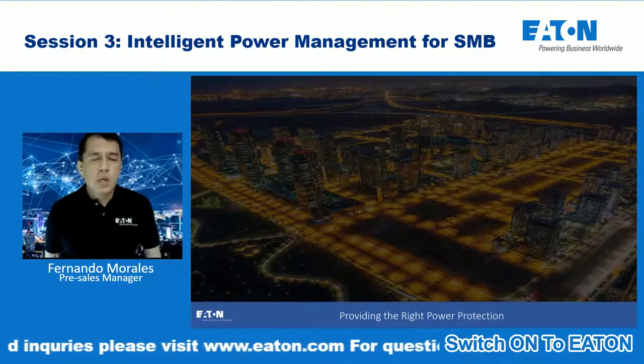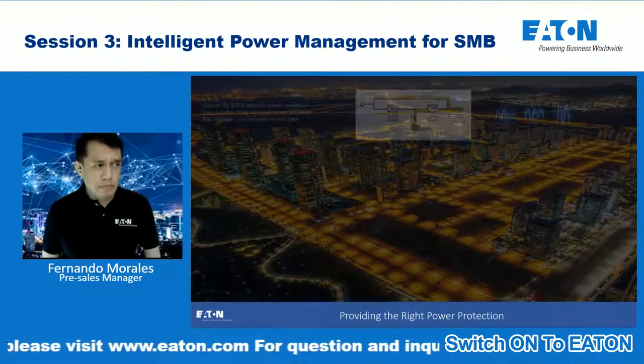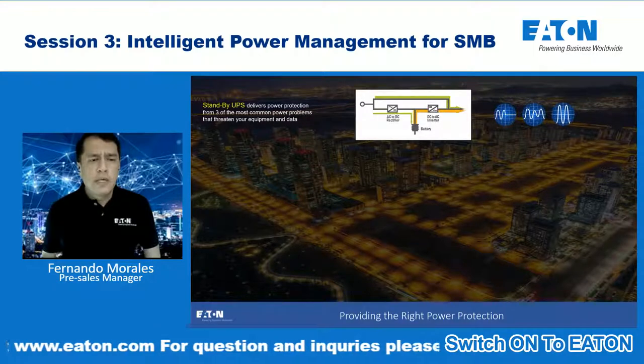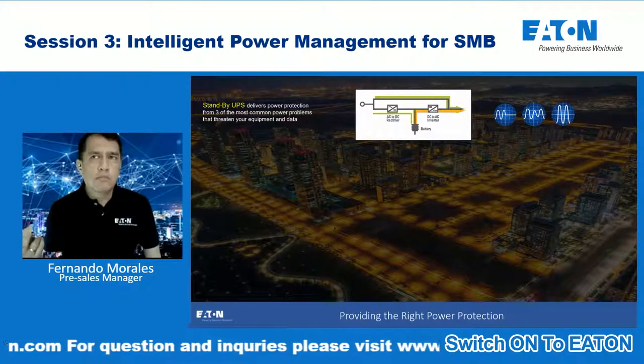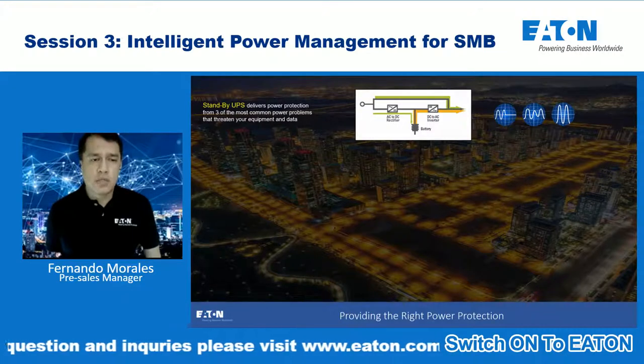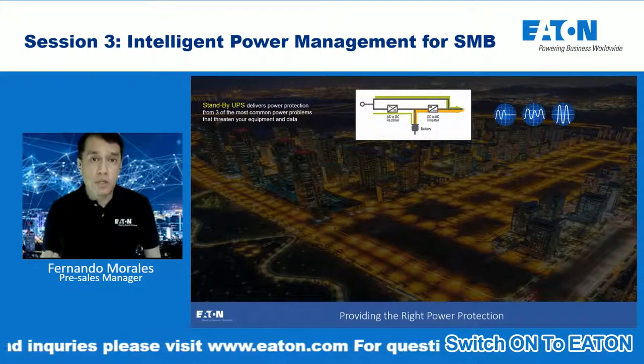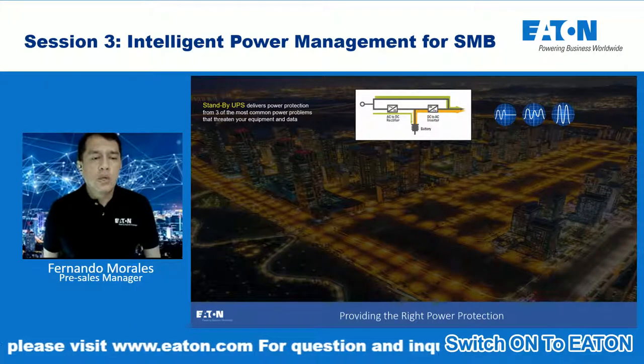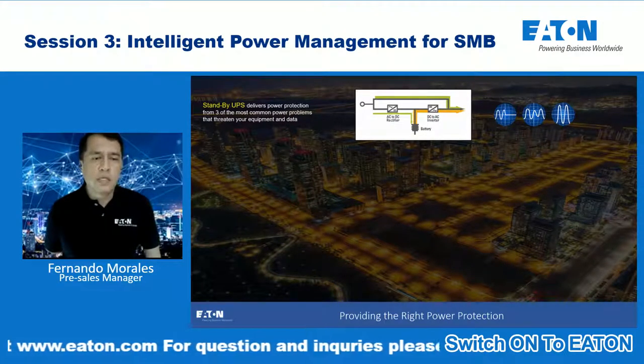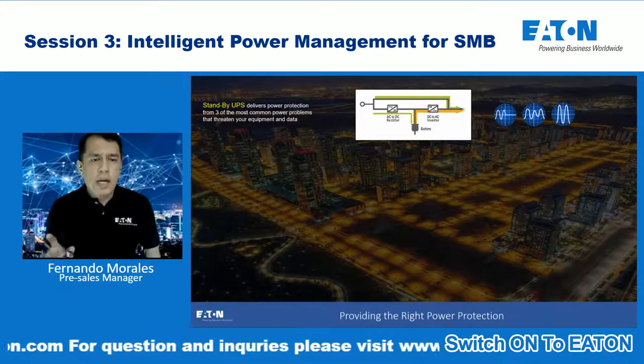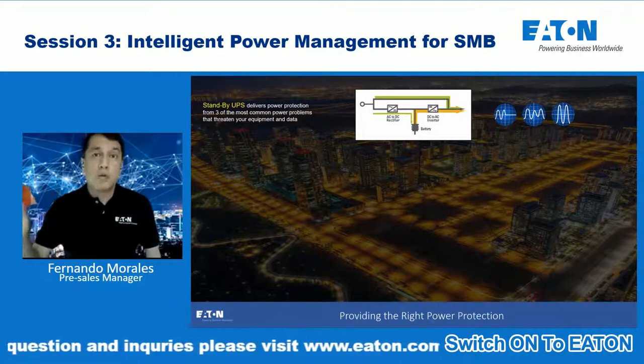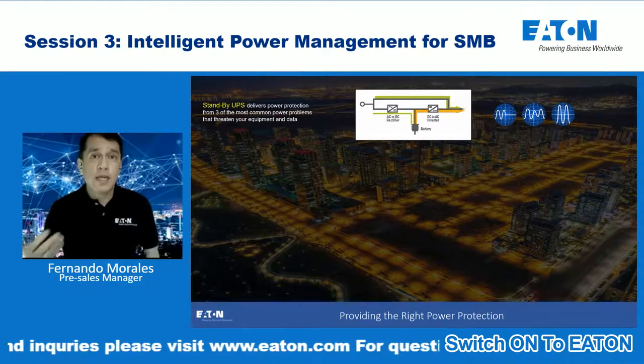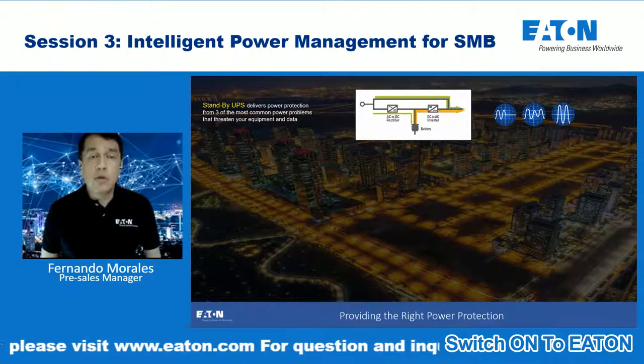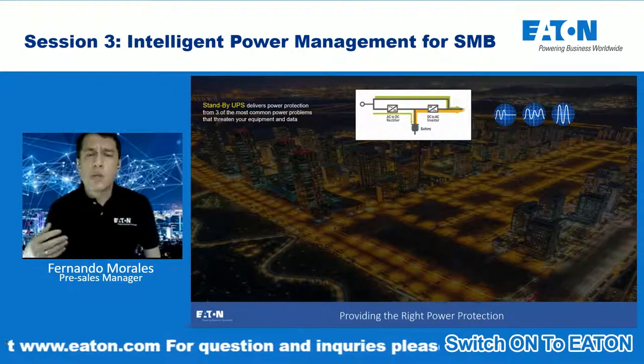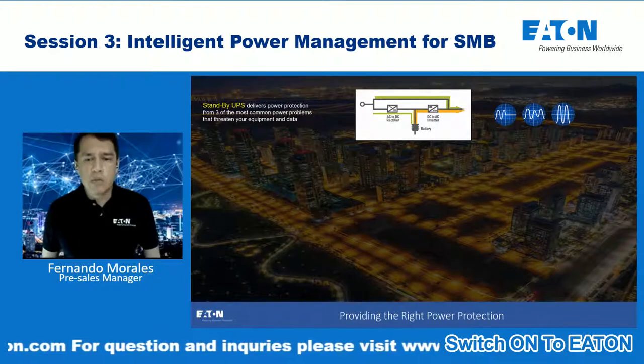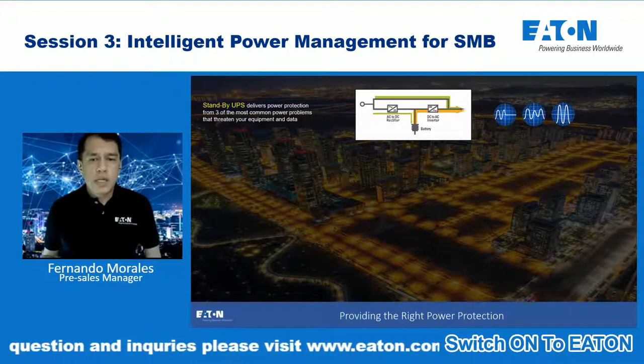As you can see on the screen, we have two common topologies for a UPS. One is what we call the single conversion or offline system. In a single conversion or offline UPS system, in normal operation, the power coming from our utility, from Meralco, is being fed directly to our critical loads, like our computers, laptops, and control systems in a manufacturing environment, up to a predefined limit.